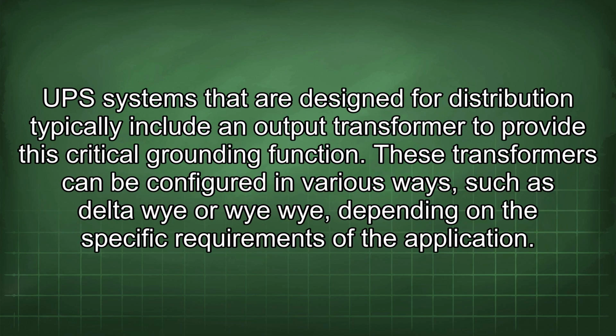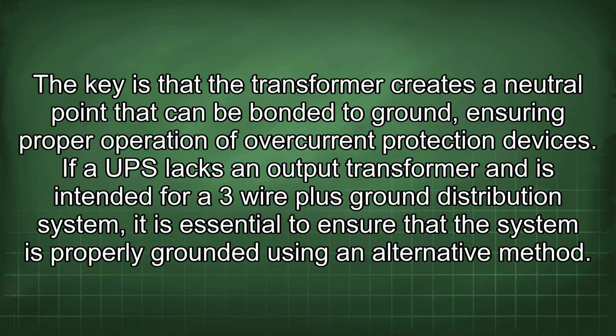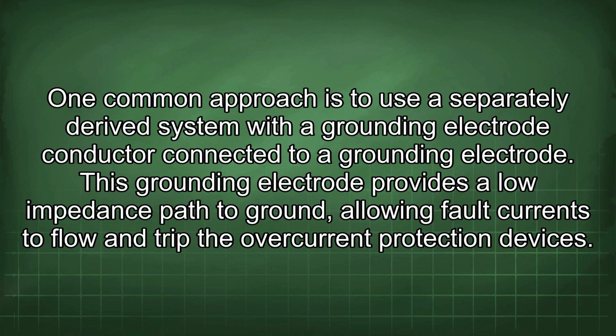UPS systems that are designed for distribution typically include an output transformer to provide this critical grounding function. These transformers can be configured in various ways, such as delta Y or YY, depending on the specific requirements of the application. The key is that the transformer creates a neutral point that can be bonded to ground, ensuring proper operation of overcurrent protection devices. If a UPS lacks an output transformer and is intended for a 3-wire plus ground distribution system, it is essential to ensure that the system is properly grounded using an alternative method. One common approach is to use a separately derived system with a grounding electrode conductor connected to a grounding electrode.